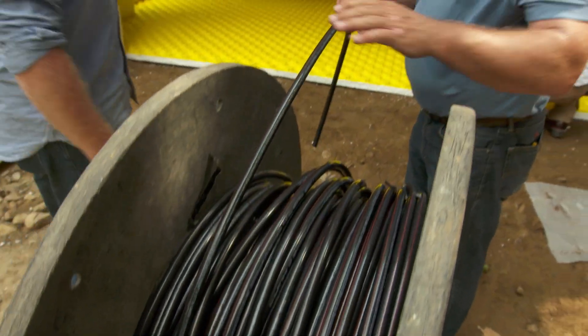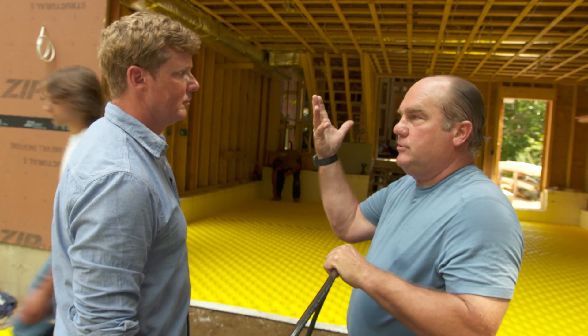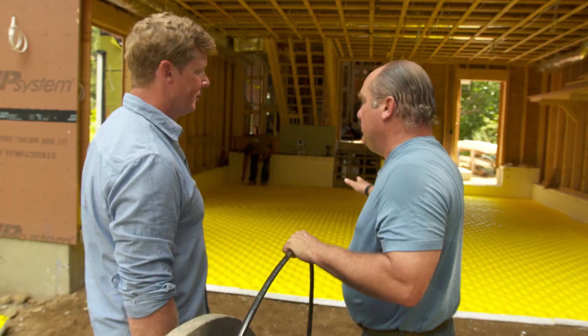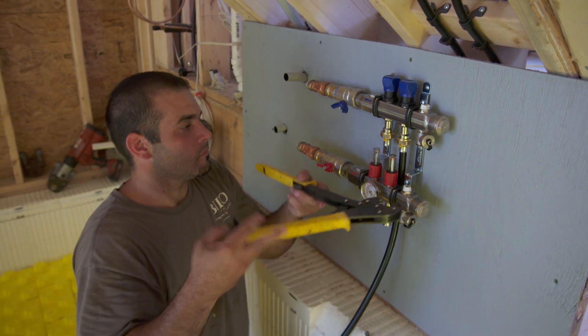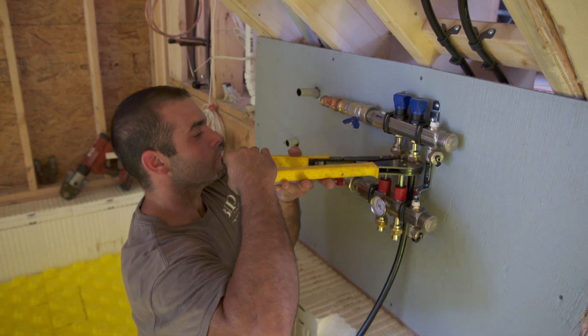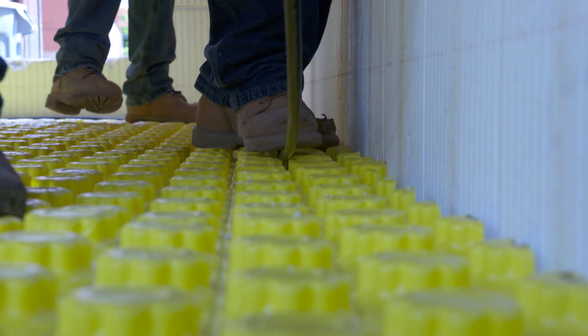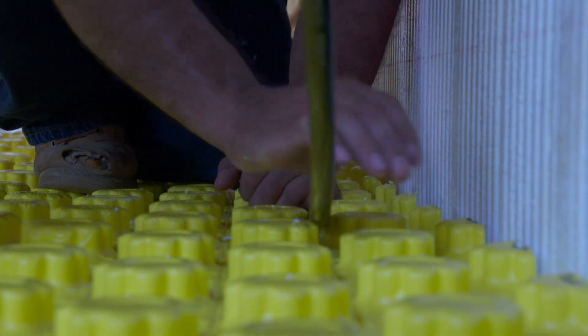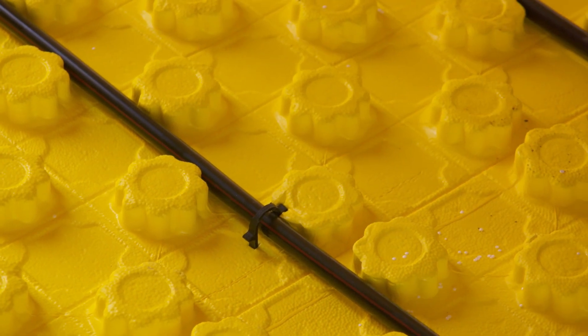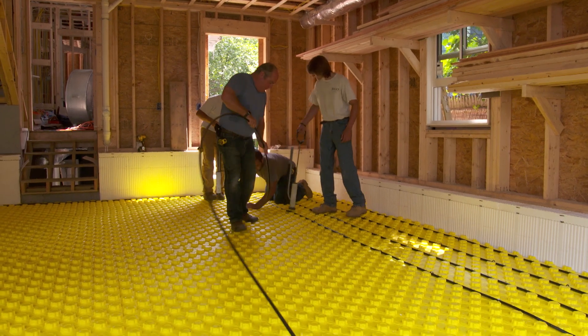The tubing we're using is a super plastic called PEX. We've used it before — from underneath the floor last year, in bathrooms, kitchens. It's just a perfect application in concrete. It's a plastic that won't get brittle over time and doesn't kink readily. You want something you can trust in the floor. The grid system comes in with three inches between each one of these nubs where the tubing's going to snap in, so we could make the tubing spacing six inches or nine inches on center.